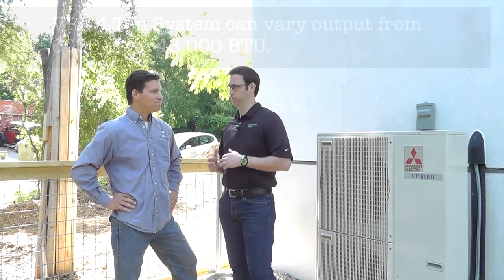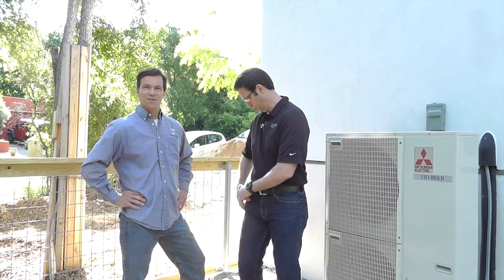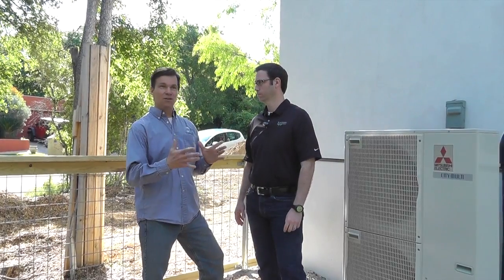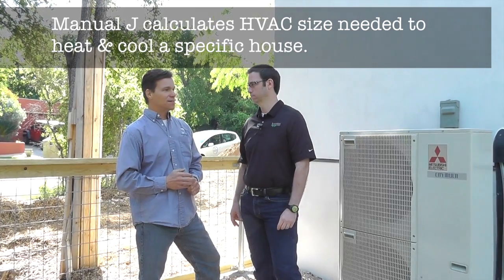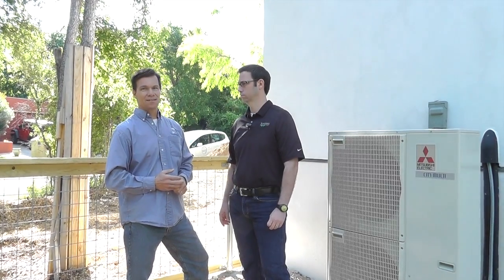When we're designing an HVAC system in Texas, tell us about the Manual J and how we decide on the capacity needed for the house, and how VRF systems actually meet the demands of a high-performance house better than a standard 2-speed outside compressor. The Manual J is often referred to as a load calculation — more precisely, it's a peak load calculation. The Manual J load is representative of the peak heating and cooling loads you're going to see in this climate zone throughout the year. What that's not saying is that most of the time — the vast majority of the time — this building will not see loads that high. It will see loads at what we call part-load conditions. This equipment and its ability to give variable capacity will be able to meet part-load conditions very efficiently.